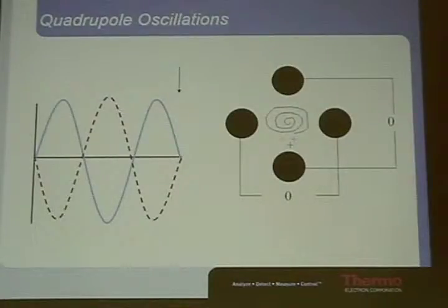If we look at the instrument lengthwise, our skimmer is always grounded at 0 volts. Our trap's always at negative 10 volts. Our poles gradually go downhill. So we might be at 0 volts, the Q00 might be negative 3 volts, the Q0 might be negative 4 volts, the Q1 might be negative 5 volts, and the trap will be negative 10 volts. See how the ions roll downhill? So that's the DC offset. The DC offset provides the forward motion.